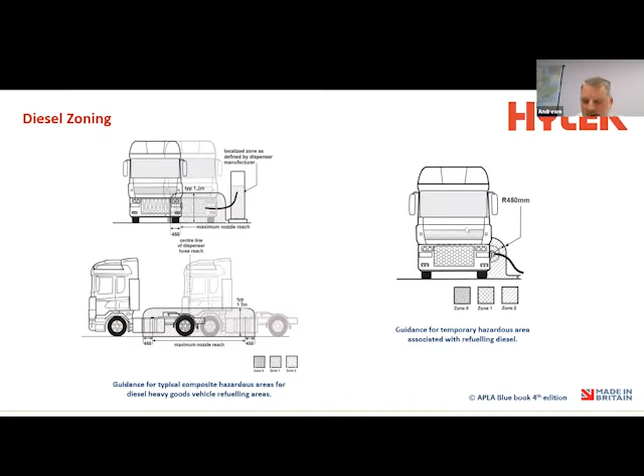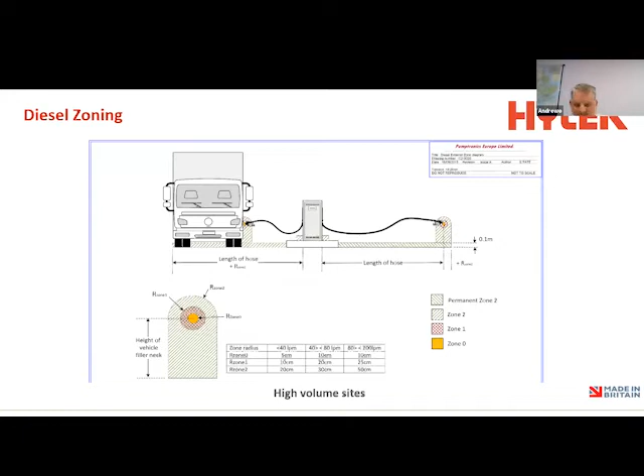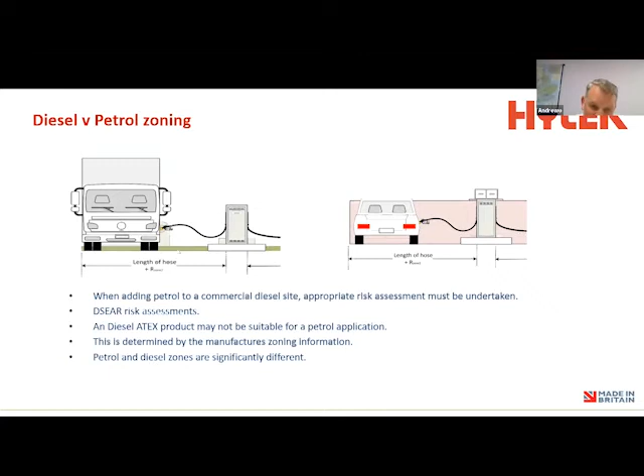Again, if we turn around and simplify that and look at the diesel zones, when we looked at the petrol side, we would have had a zone coming up towards the top of the pump. So diesel does have a hazardous zone, but it's a lot less onerous than petrol, but it does need to be considered. So if we just look at a simple overview here, we can see here we are with the petrol zones. Diesel does have a zone, but you can see the extent is a lot less.